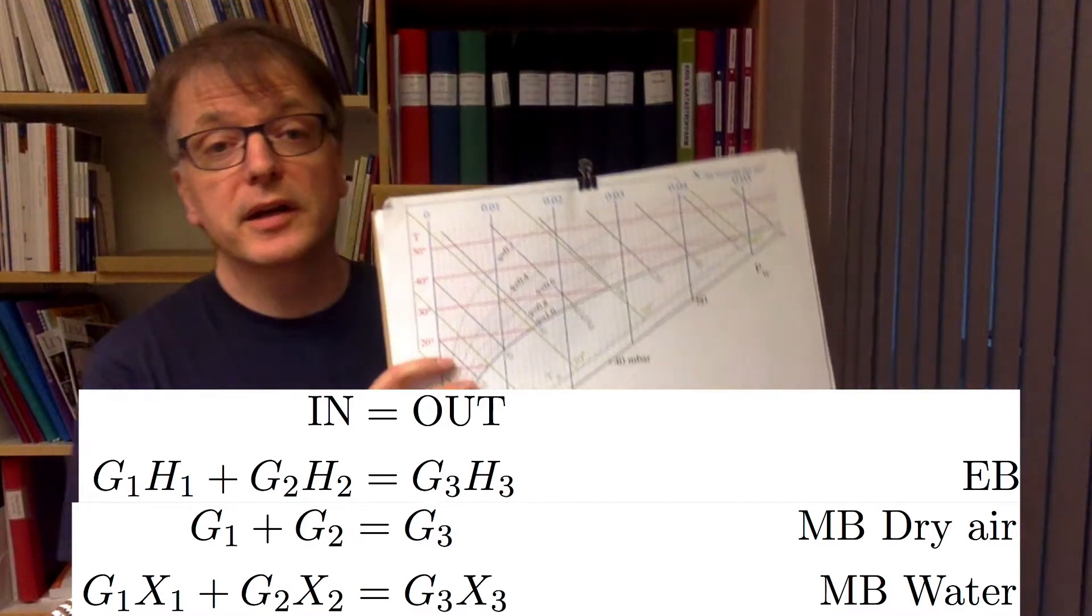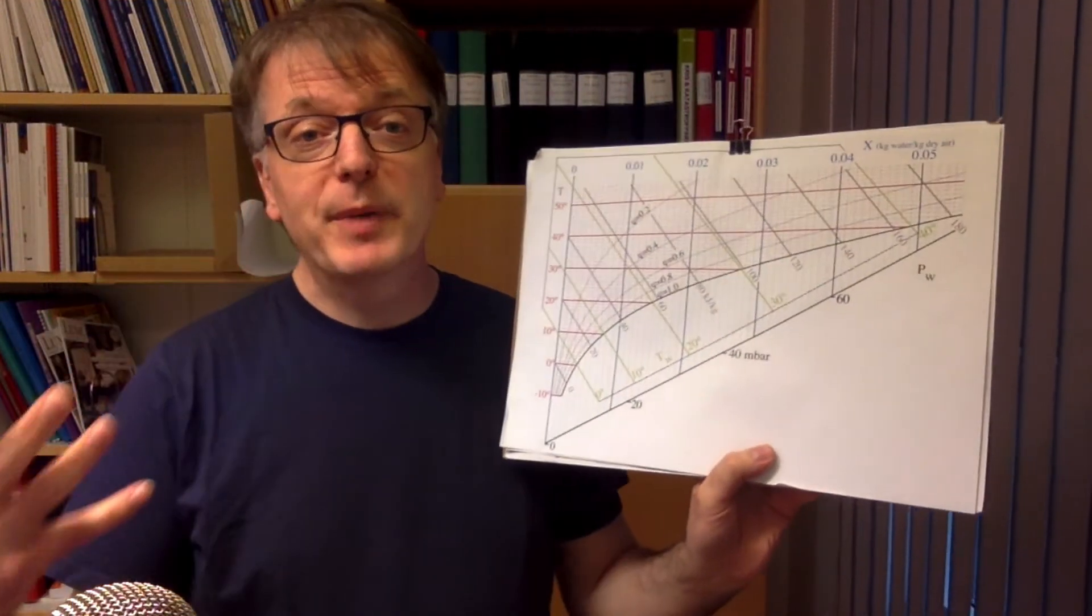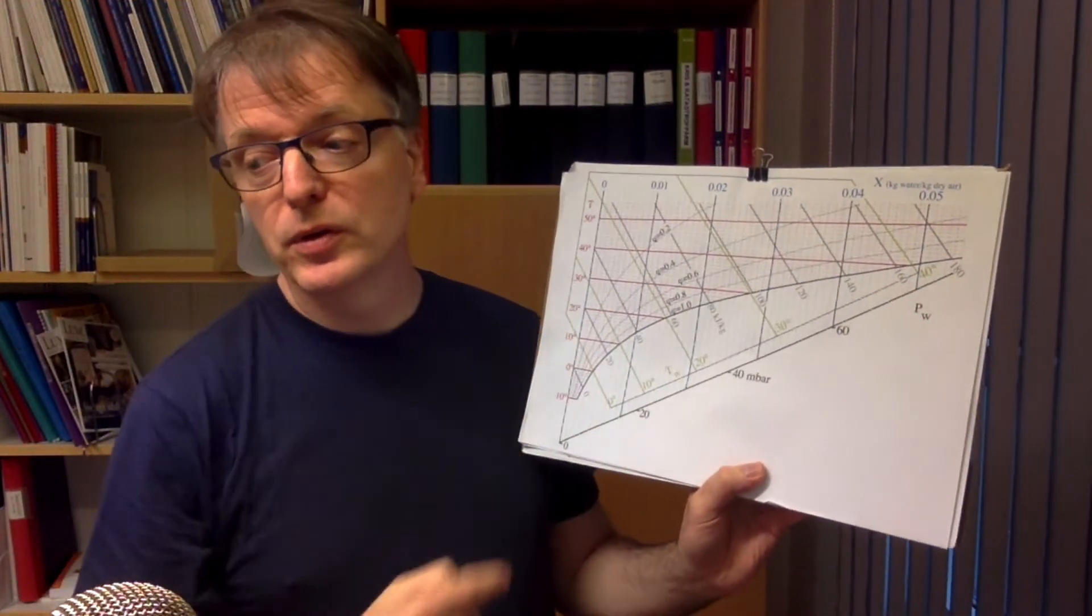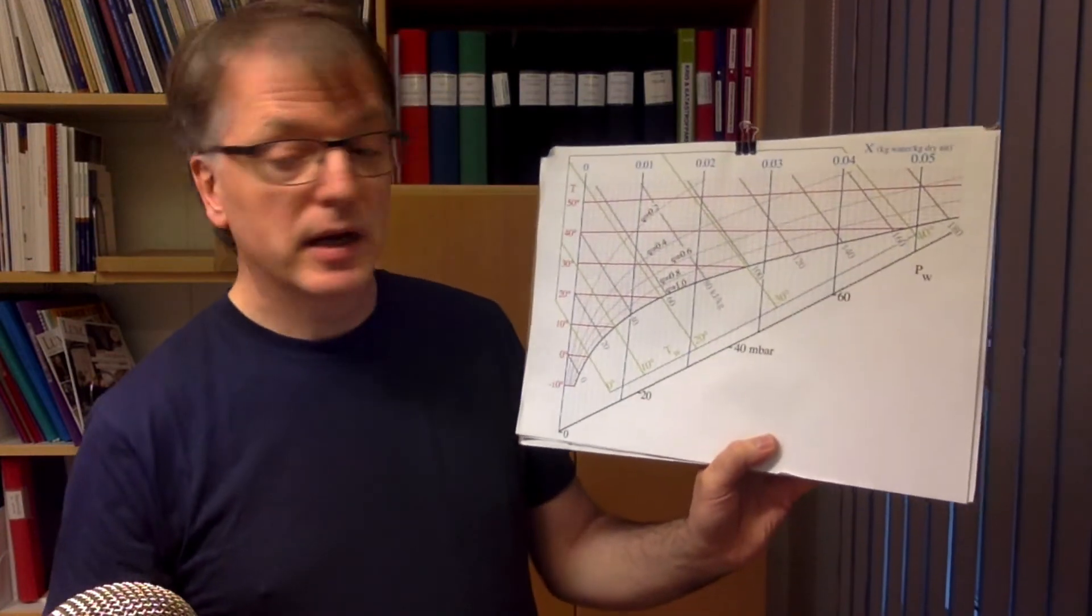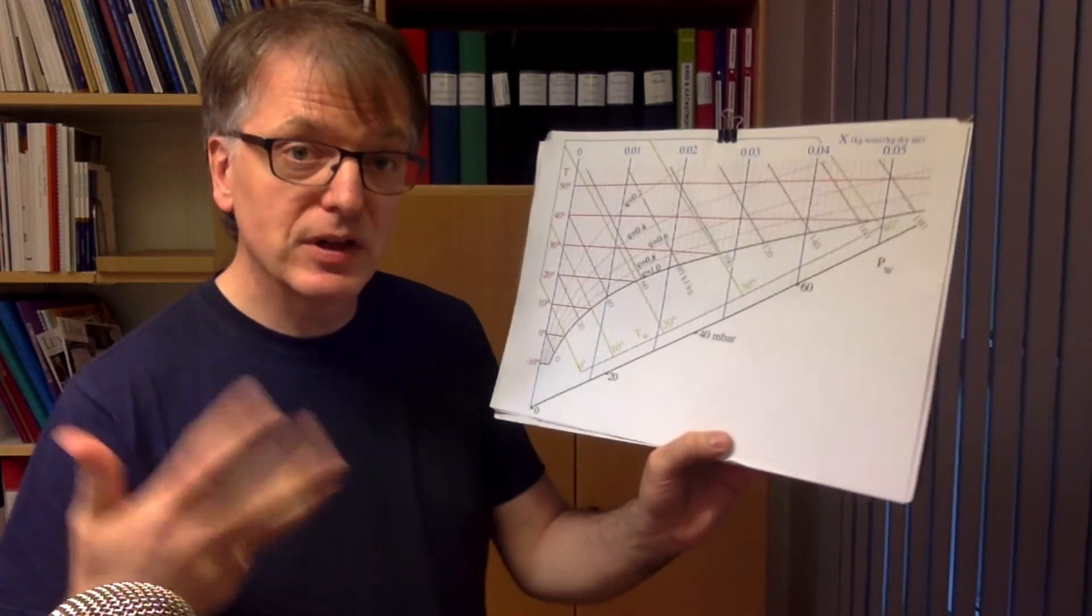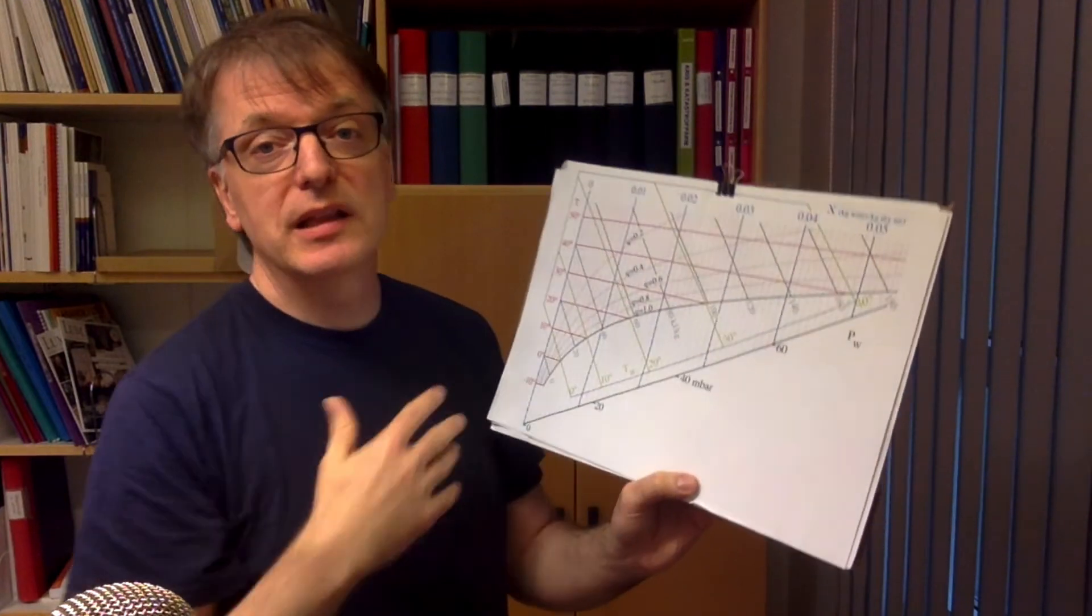A nice feature with the Mollier diagram is that if you have adiabatic mixing and you find the two points of the two air flows in the Mollier diagram, the solution, the result of the mixture, will be on a straight line between the two.